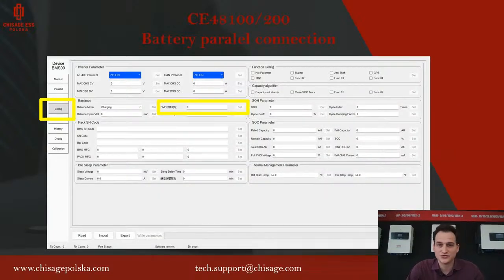So we have to use the JBD software, go to config, and in this yellow frame in the middle we have the BMS, so we have to put the address manually. For battery number 1, we go with number 1 and set. For battery number 2, we go with 2 and set. So master, of course, is number 1, and the other batteries 2, 3, 4, in order, we connect to this master.